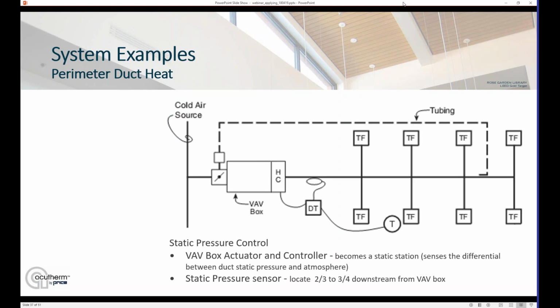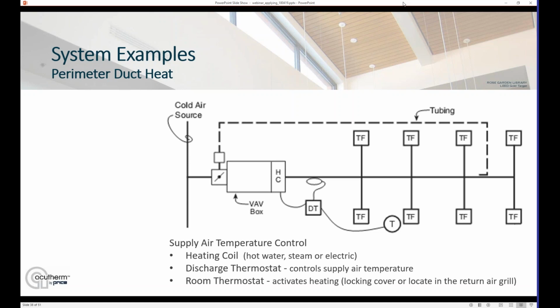VAV boxes, especially in retrofit situations, can be relatively easily converted to a Therma-Fuser diffuser approach. One, creating the static pressure control by using the VAV damper already in the box. A lot of times you can even use the controller that's on the box by porting the high side of the differential pressure sensor downstream in the ductwork, leaving the low side open to atmosphere, and now you are measuring static pressure. Temperature control using the coil in the box. Again, great if you can get a discharge temperature sensor on it to control that, whatever that source of heat is, and then a room temperature sensor to know when to turn the heat on and off again.